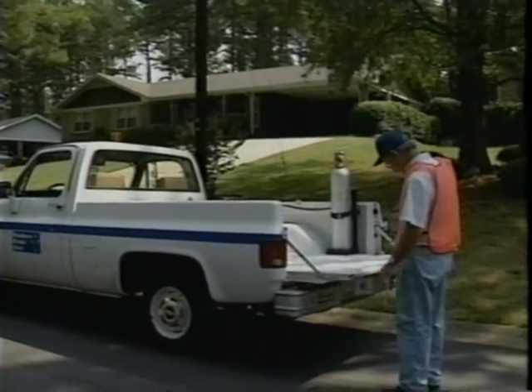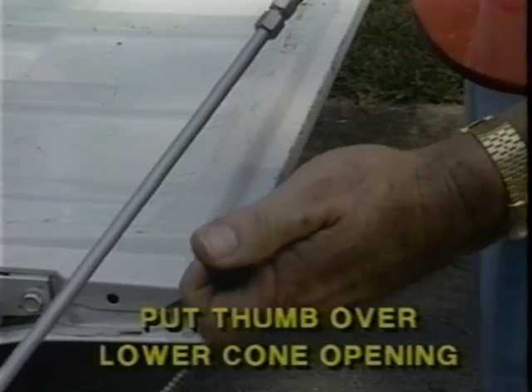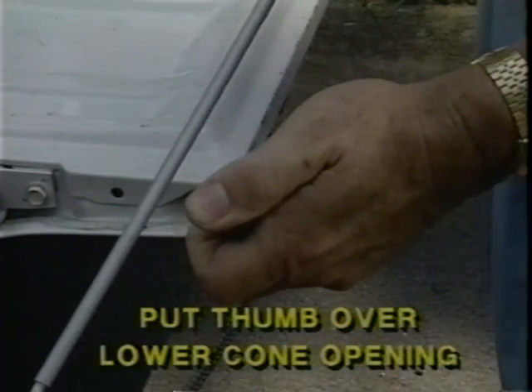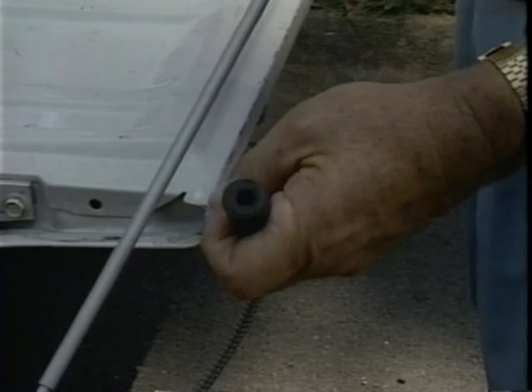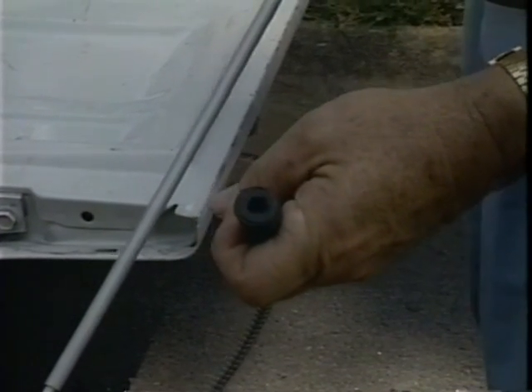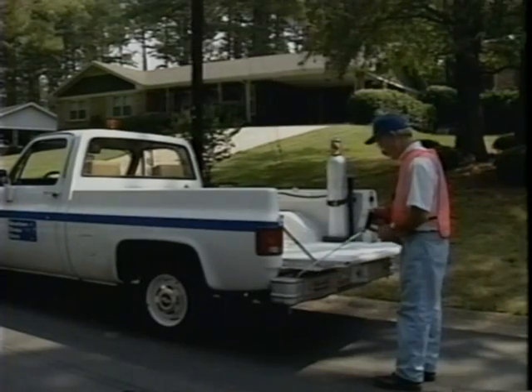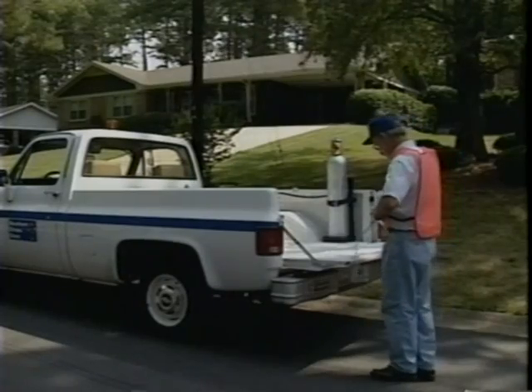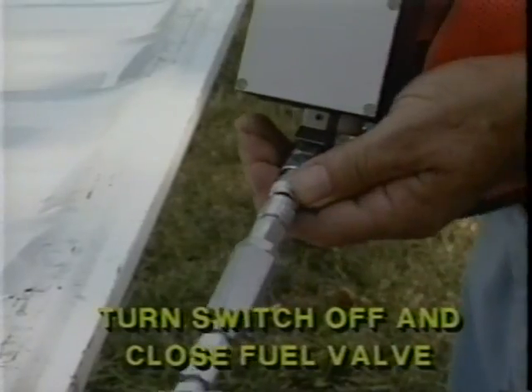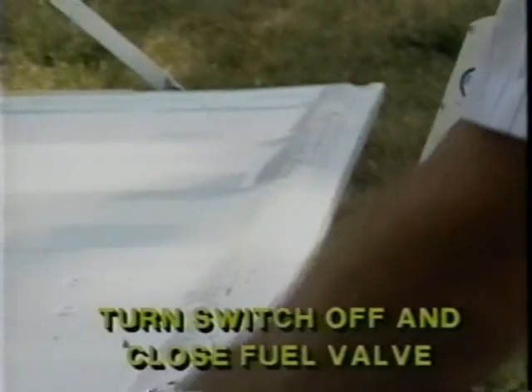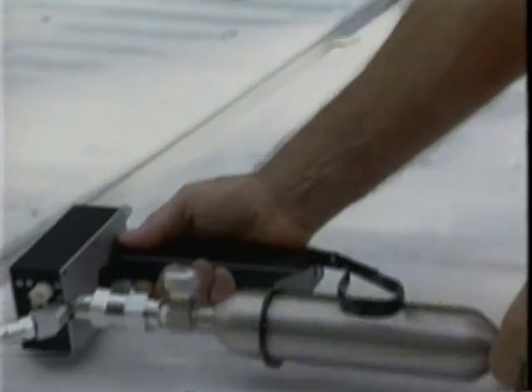When shutting down the FlamePack 400, place your thumb over the lower cone opening. This will stop airflow and put out the fire. Both the audio and visual alarm should come on as flameout occurs. Turn the switch to the off position and close the fuel flow valve. It will take a few seconds for the fuel flow to completely stop.